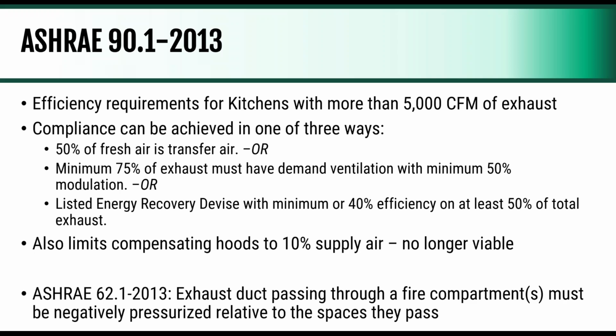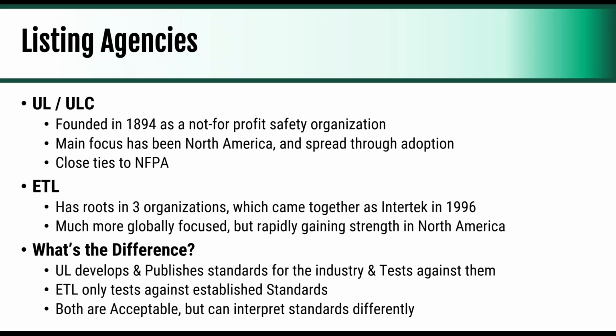We sell engineered grease duct, and that's one of the real reasons when we talk about that's all been tested and listed, whereas field fabricated ductwork is put together in the field. Listing agencies. We work mainly with UL, but we also do work with ETL on some things. UL is a really old organization, so they've been around since 1894. They work hand in hand with NFPA on almost all of their projects. There have been some disagreements over the years, but really, if it's in NFPA 96, chances are UL has a code and a standard written specifically for that with the reason.